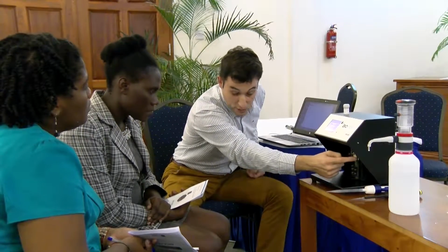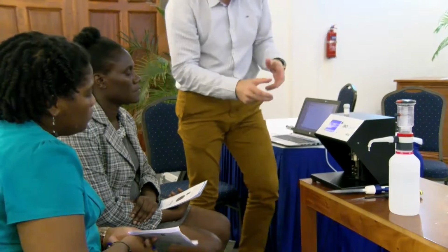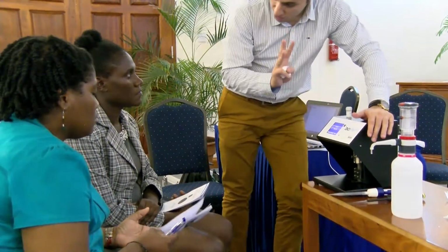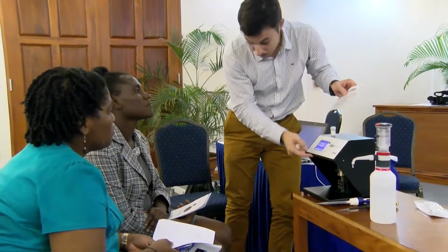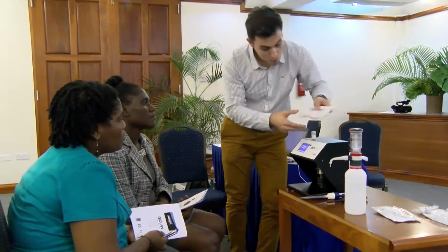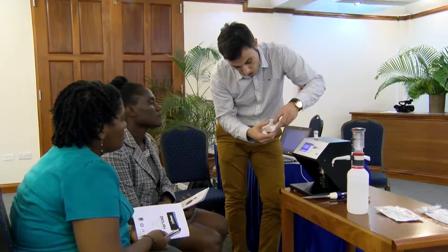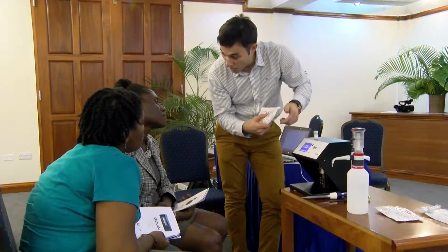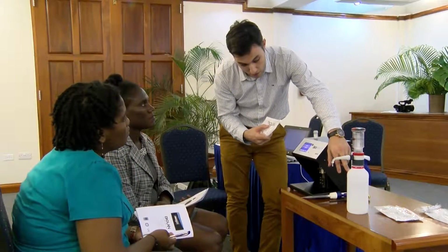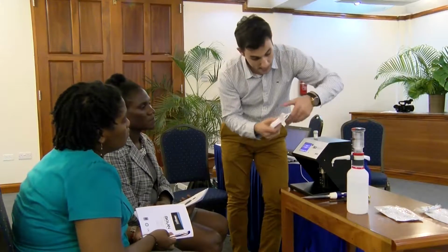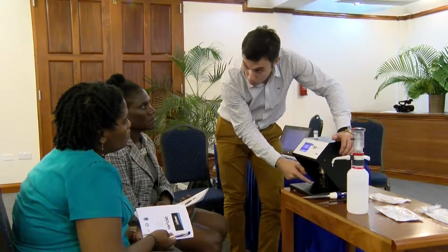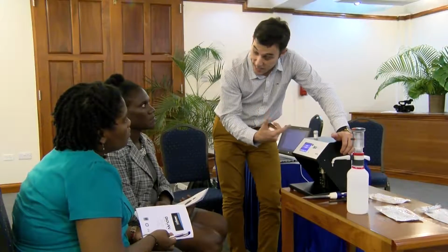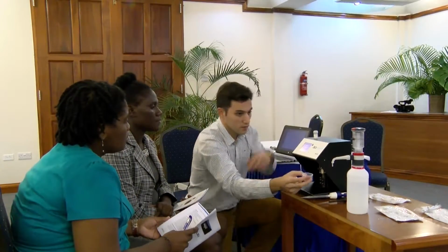Reference electrode, working electrode or biotest. We call it biotest, where the enzyme is. And now, these are the 2 main accessories to use it. Reagents. We just use 3 reagents, no more. The first is the working electrode, where the enzyme is located. Then the measurement solution. This measurement solution is provided by us. Each one of these tubes is valid for 1 liter. It must be mixed in 1 liter of distilled water. The purpose of this reagent is to supply a comfortable buffer with a suitable pH to the enzyme, so it works comfortably. This is basically a buffer.